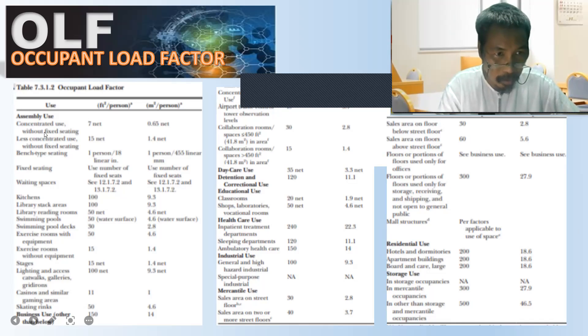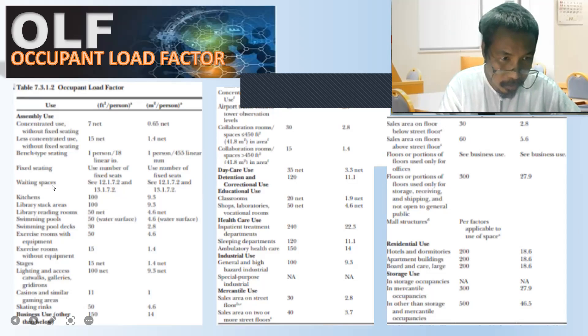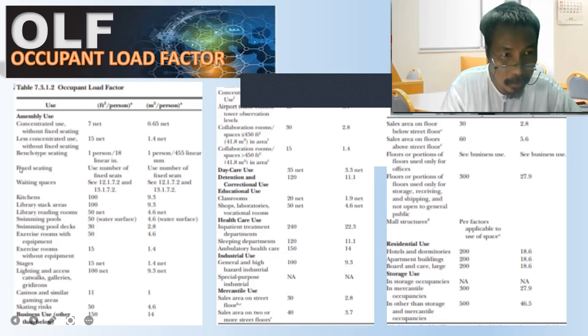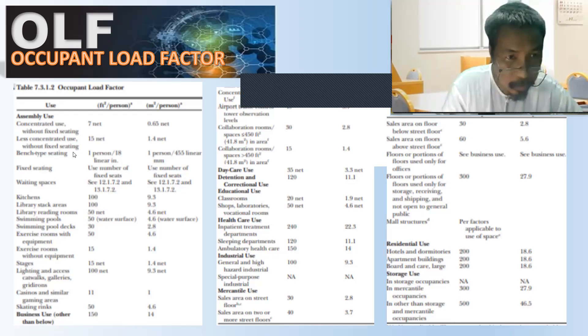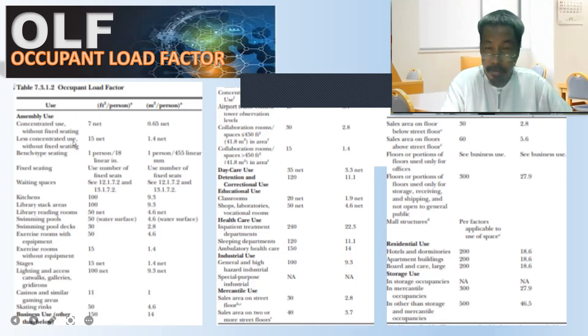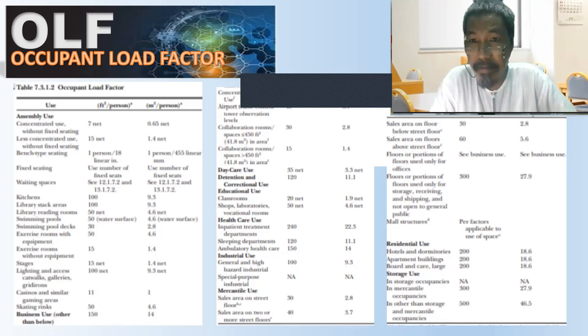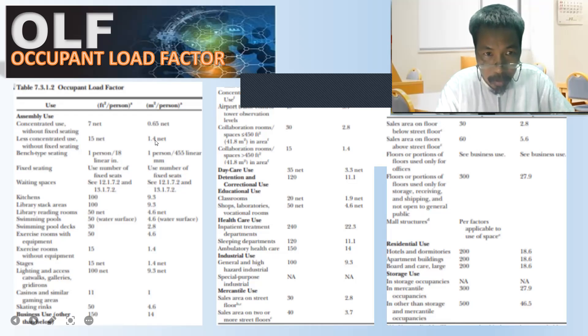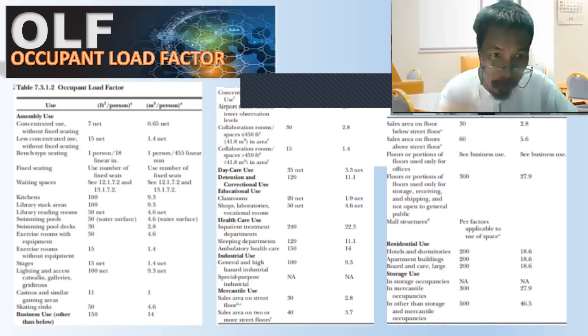For assembly use, there are different categories: concentrated use without fixed seating, bench-type seating, and fixed seating. For TCO — which is a school — the applicable category is less concentrated use without fixed seating, with an occupant load factor of 1.4 square meters per person.